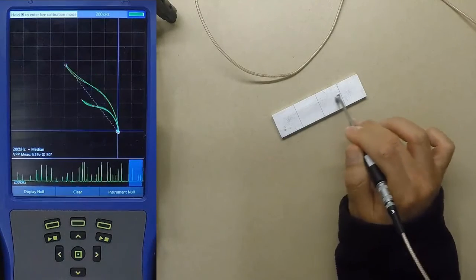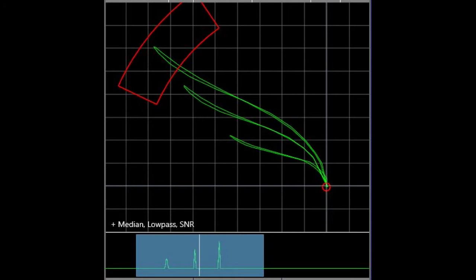If you have an alarm set based upon the screen height of the signal, then obviously this liftoff can affect the position of the signal on the screen, which lessens the reliability of the alarm.